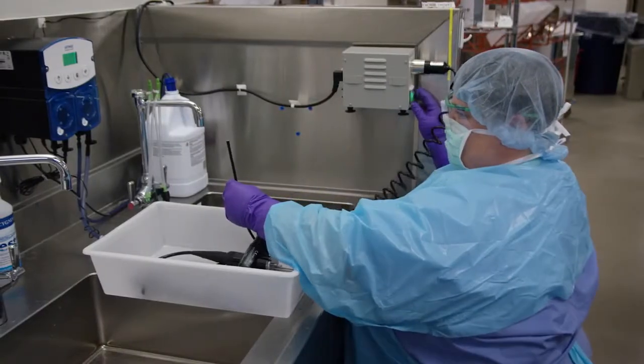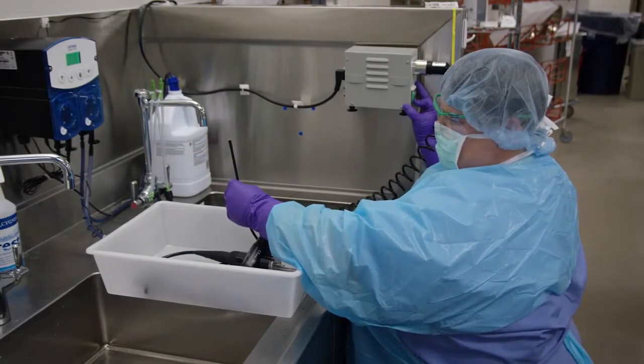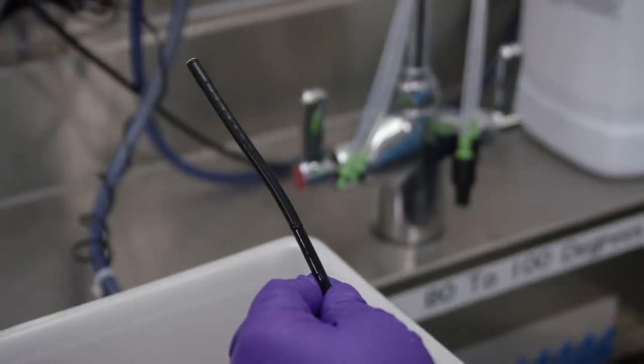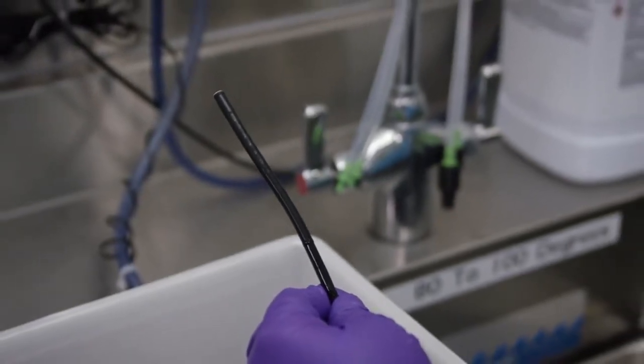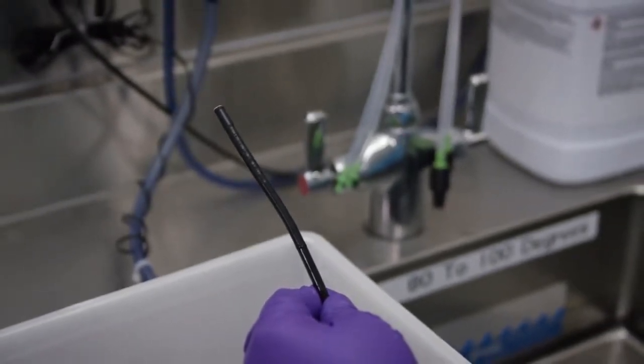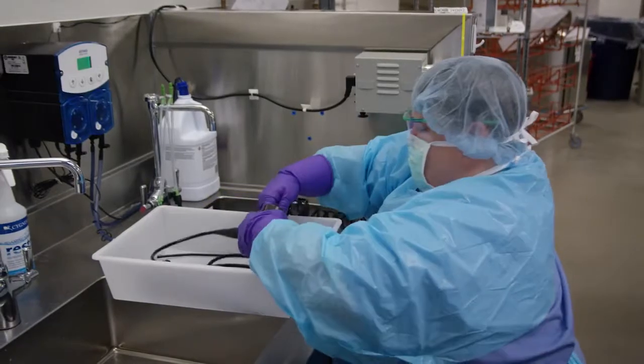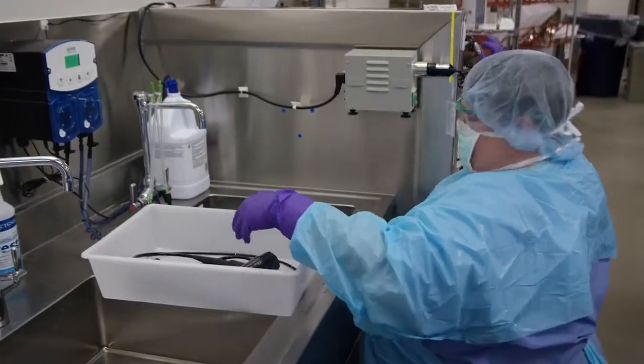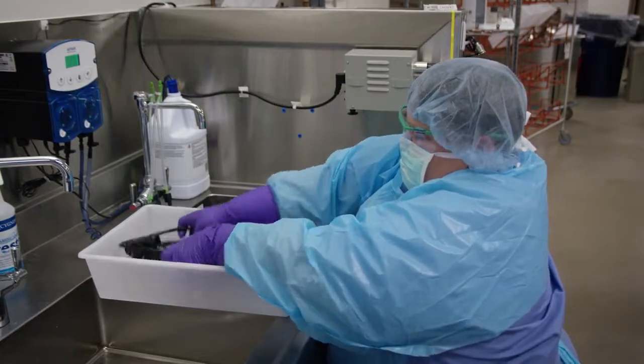Turn off the tester, which releases pressure from inside the scope, and verify deflation of bending rubber at the distal end of the scope. Disconnect the leak tester from the endoscope. Continuous air pressure prevents water from entering internal portions of the scope, causing damage.